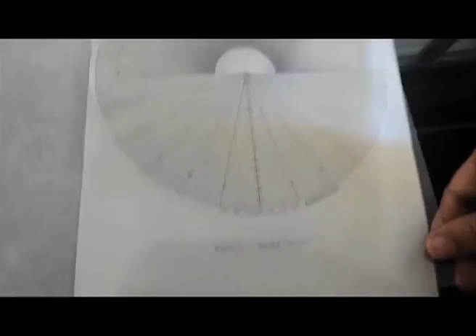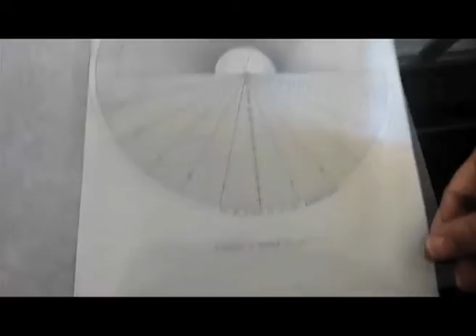Now you can see the shadow of one edge of the workpiece is coinciding with the zero line, and the other edge of the shadow is coinciding with the 45-degree line. So the wedge angle on the workpiece is 45 degrees. Like this, we can use the chart gauges for measurement of angles. So this is the complete view of a chart gauge. Radius can be measured, as also angles can be measured using this particular chart gauge.